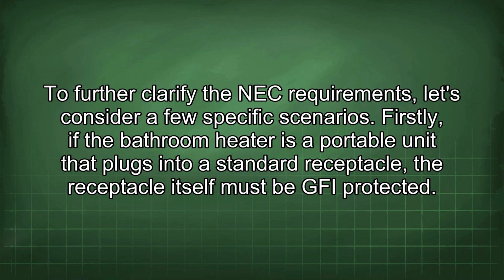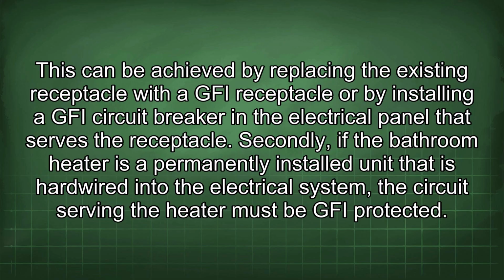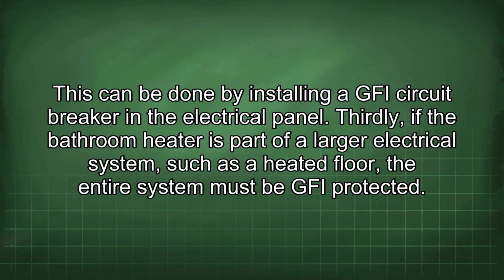Firstly, if the bathroom heater is a portable unit that plugs into a standard receptacle, the receptacle itself must be GFI protected. This can be achieved by replacing the existing receptacle with a GFI receptacle or by installing a GFI circuit breaker in the electrical panel that serves the receptacle. Secondly, if the bathroom heater is a permanently installed unit that is hardwired into the electrical system, the circuit serving the heater must be GFI protected. This can be done by installing a GFI circuit breaker in the electrical panel.